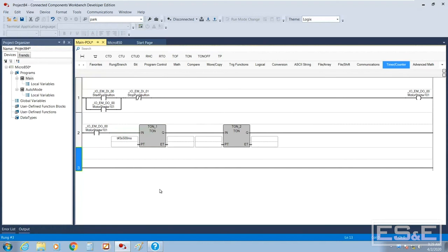Within the CCW environment, if you have to do that same add instruction with those three things that you're working with, you have to make them all the same data type. So we have data type conversions that are just automatically done for us in the other editors. Here we have to manage those data types, and that does include time. So I can't just move a tag value into the preset of timer 2 and be able to modify it. Let me show you what I'm talking about.